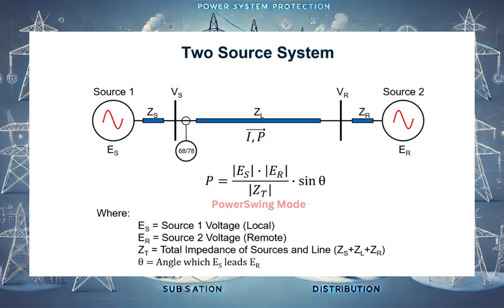This power swing — the uncertain behavior of the power system with impedance changes — is seen by impedance protection relays on the transmission line. These relays might incorrectly interpret the swing as a fault. To handle this, impedance relays have a power swing feature that detects the condition and treats it as a power swing rather than a fault, blocking the impedance operation for a certain period of time.